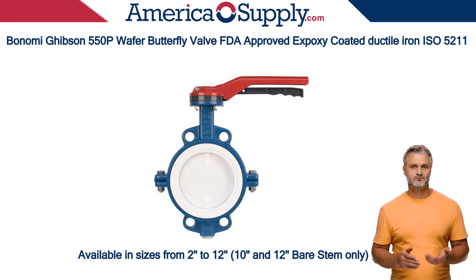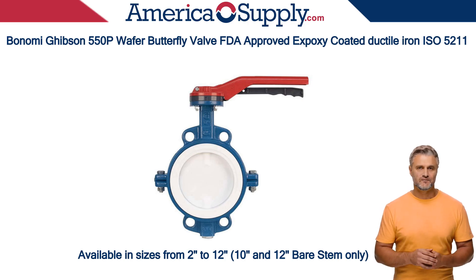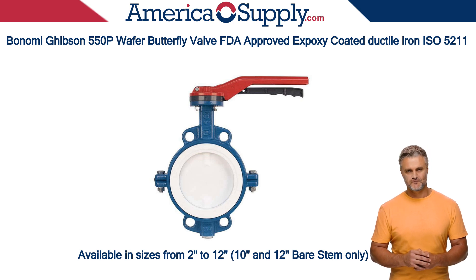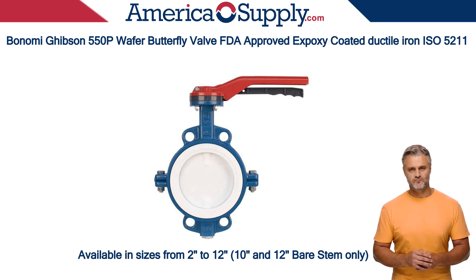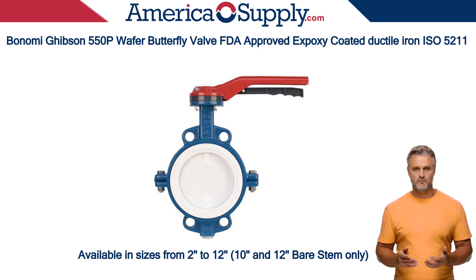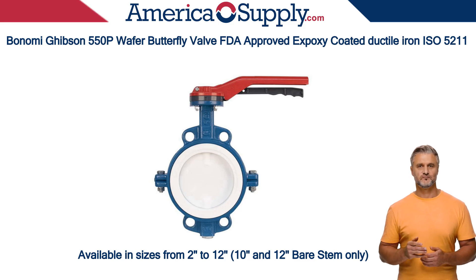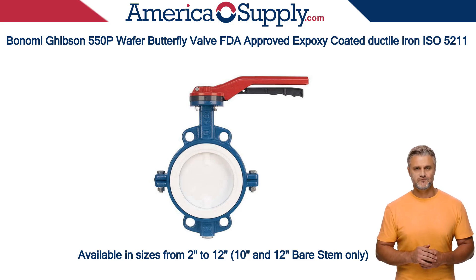The Ghibson 550P's construction is centered on durability and performance. The body is made from ductile iron, ENG JS 400-15, and is coated with an epoxy finish. This combination provides excellent strength and corrosion resistance. Wafer-style valves are designed to be sandwiched between two pipe flanges, held in place by bolts that pass through the valve body.